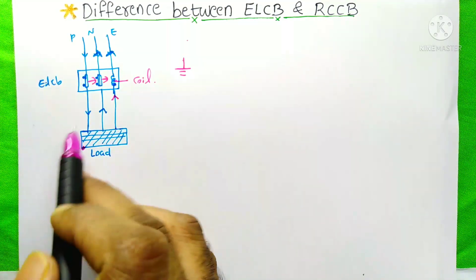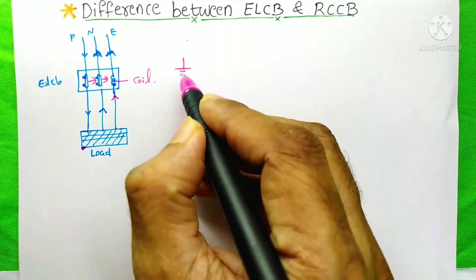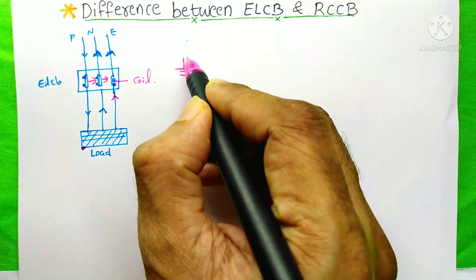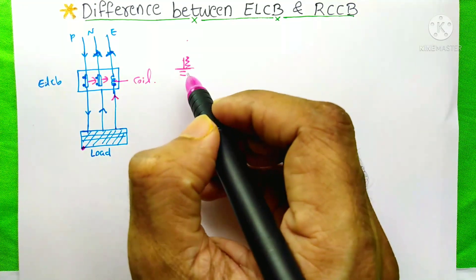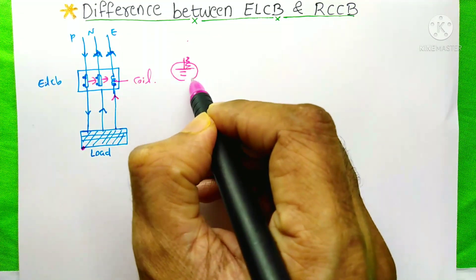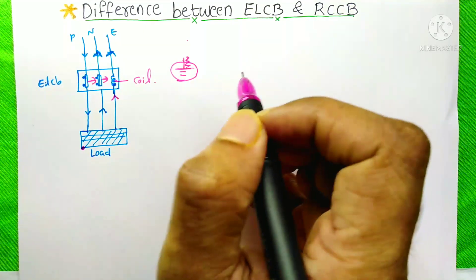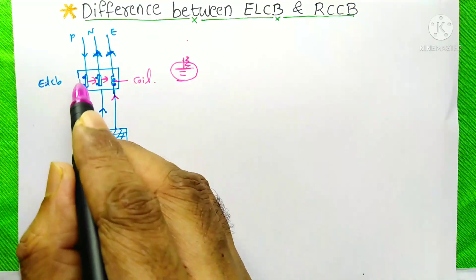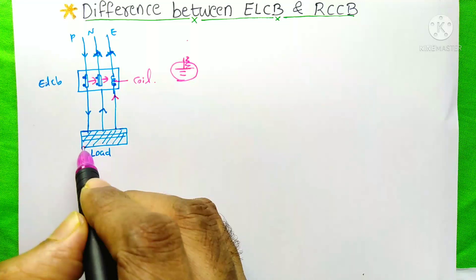There are some problems related with this ELCB. Suppose at your house, your earth connection is broken, or your earth pit loses the property of good earthing. At that time, even if this phase touches this body, the current will not go through this earth.